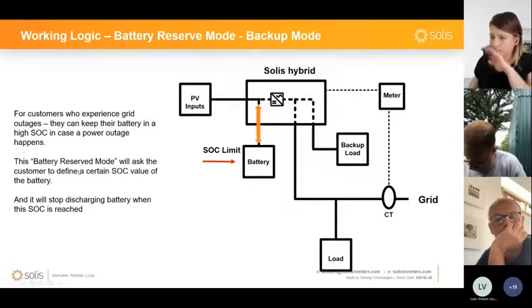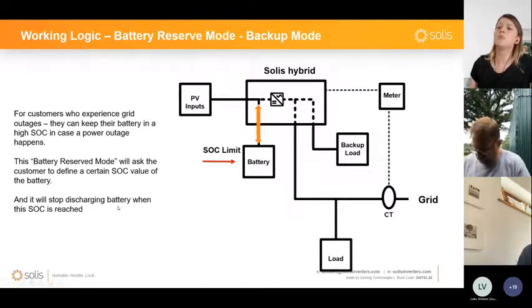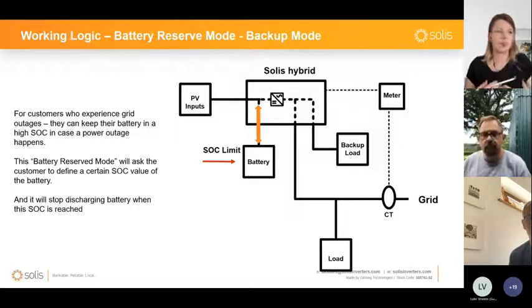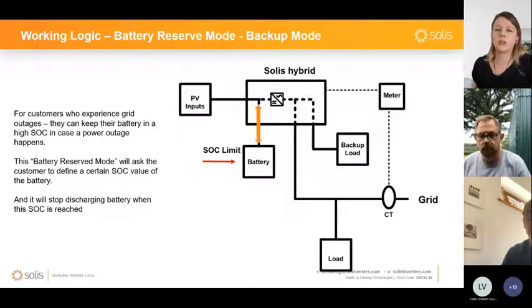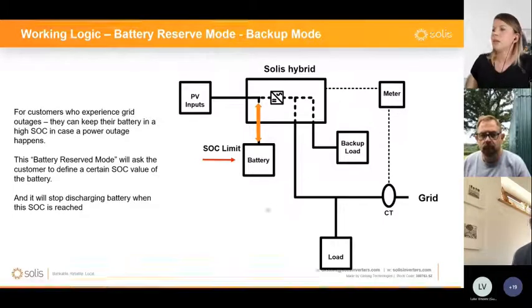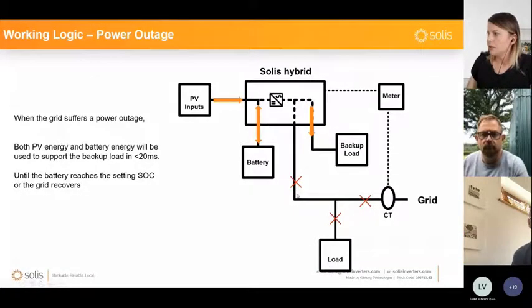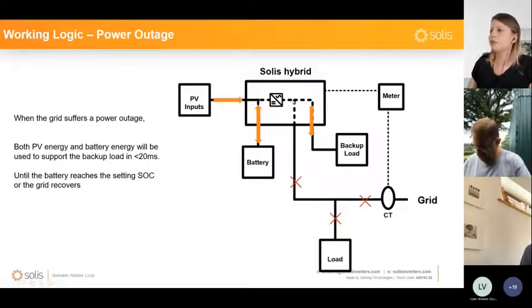So when you are in battery reserve mode and you are selecting this mode, you are asked to define an SOC value below which the hybrid inverter will not discharge the battery when it has a grid connection available, and it will keep it as a reserve in case there's a grid outage. So when this happens, when there's no connection to the grid, just the backup loads will be supplied from the PV and from the battery.